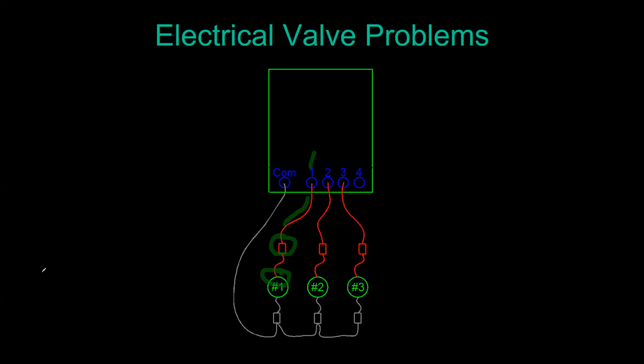Very, very simple. If it's affecting all of the valves, it's a cut in the wire on your common wire, or it's this bad connection here where they're all tied together. And that's pretty much about it. It's pretty rare to have 3 solenoids die all at the very same time. Normally only go one at a time, and they can go bad, and they do need to be replaced on occasion. But normally when an irrigation valve no longer opens up, that's the first thing people do is they replace the solenoid. They notice the wire coming from the timer is all green and grungy. They clean it up, they connect it, and lo and behold, it turns on now. And then they take that perfectly good solenoid they just removed and throw it in the garbage.